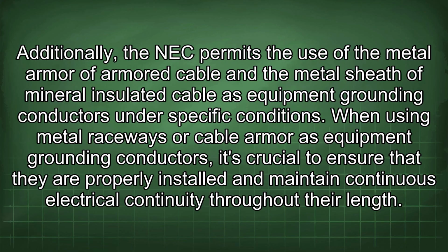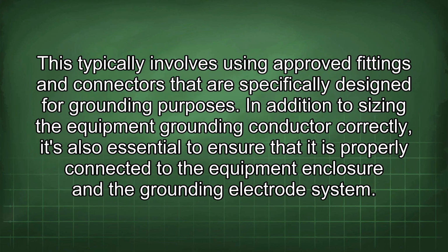Additionally, the NEC permits the use of the metal armor of armored cable and the metal sheath of mineral insulated cable as equipment grounding conductors under specific conditions. When using metal raceways or cable armor as equipment grounding conductors, it's crucial to ensure that they are properly installed and maintain continuous electrical continuity throughout their length. This typically involves using approved fittings and connectors that are specifically designed for grounding purposes.